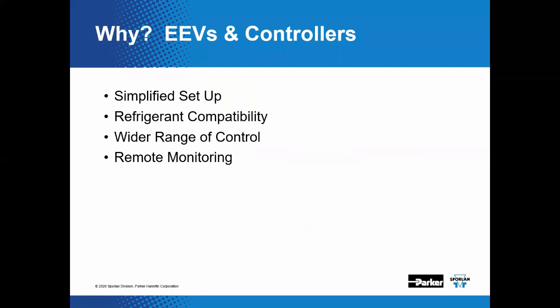But before we go any further, the question comes up, why consider the electric valve and the necessary controls that go along with it? Well, here are a few reasons. The commissioning process is much simpler. You key in or select the parameters and you're ready to go. The process to set superheat is potentially much more time consuming with the traditional mechanical thermostatic expansion valve. There's no need to unload the case. I mean, it's a pretty straightforward affair.